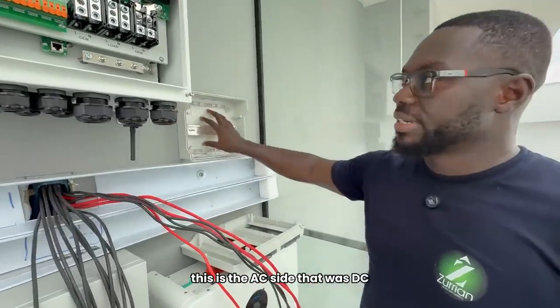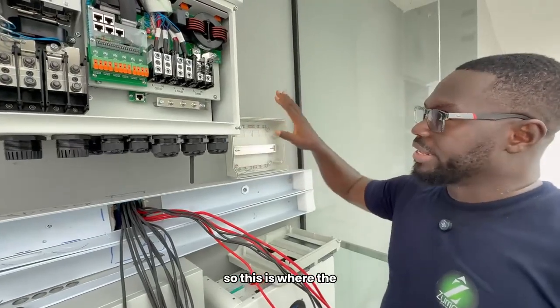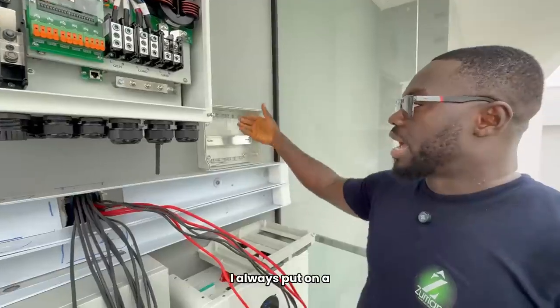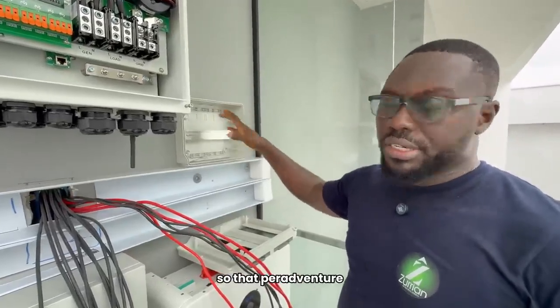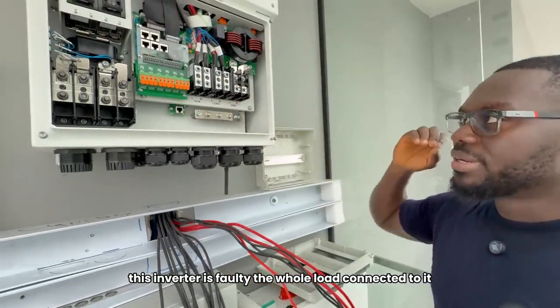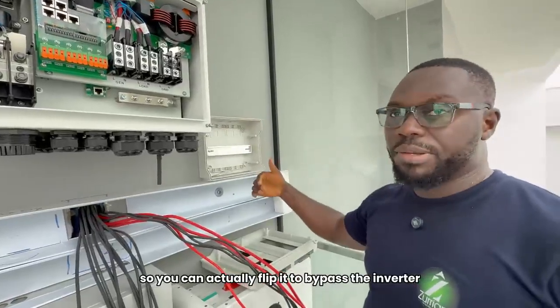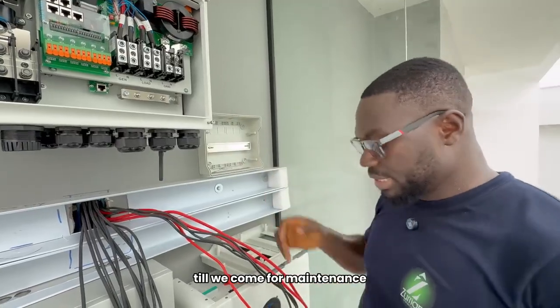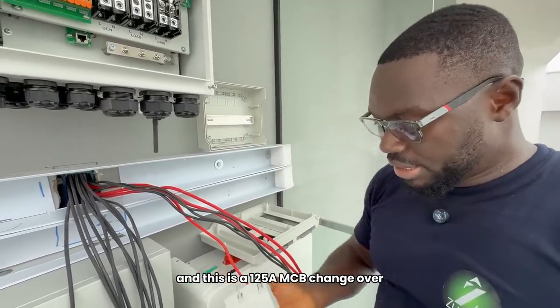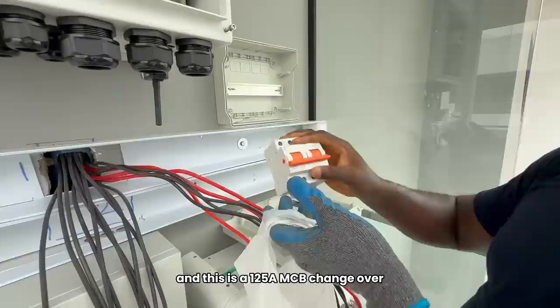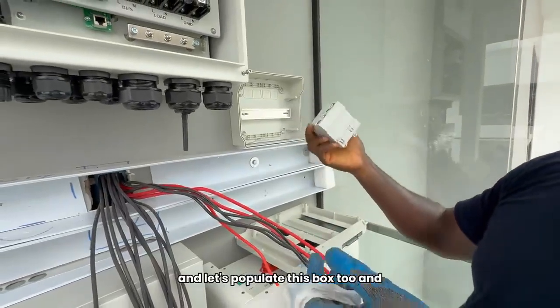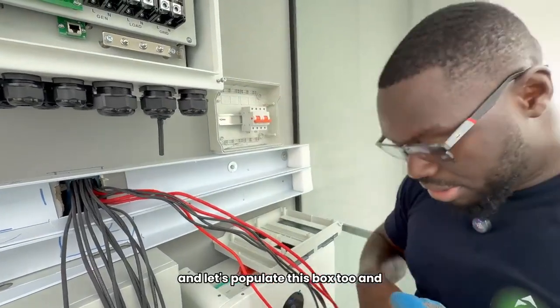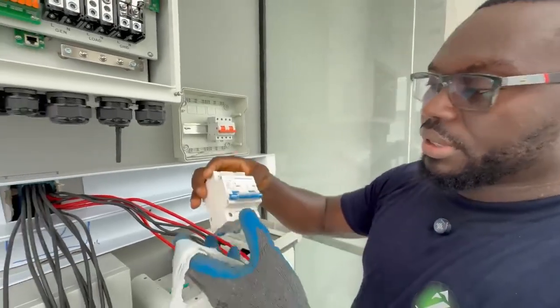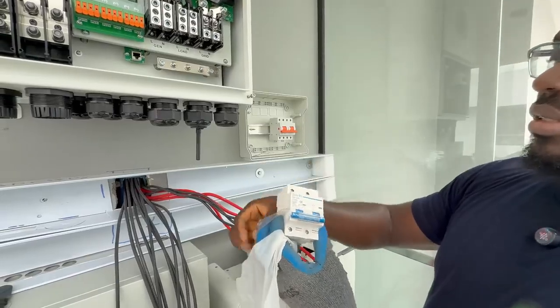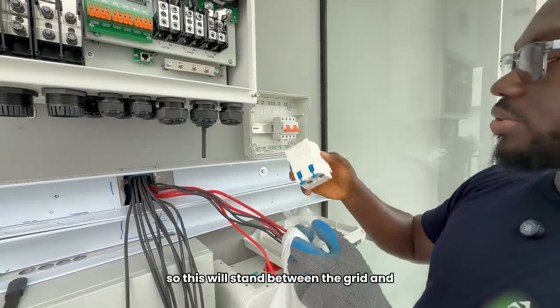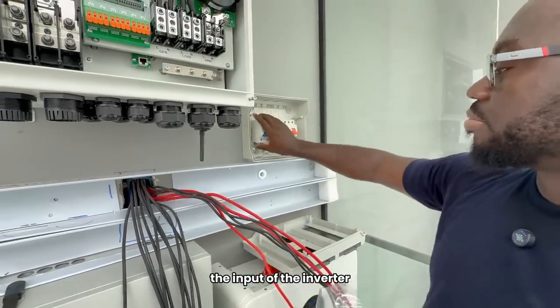This is the AC side, that was DC. So this is where the grid inputs to the inverter will be controlled. I always put a bypass changeover so that, peradventure this inverter is faulty, the whole load connected to it, people will not be in darkness. So you can actually flip it to bypass the inverter till we come for maintenance. So we'll populate this side too. And this is a 125 amps MCB changeover. And let's populate this box too. And 125 amps input breaker. So this will stand between the grid and the input of the inverter.